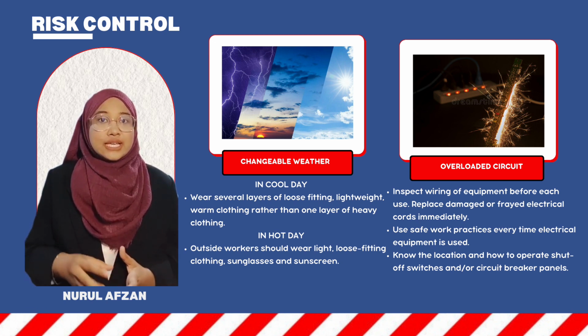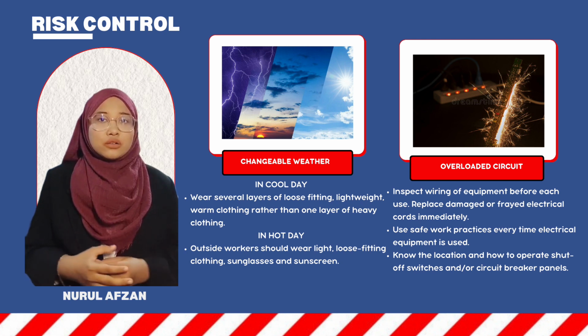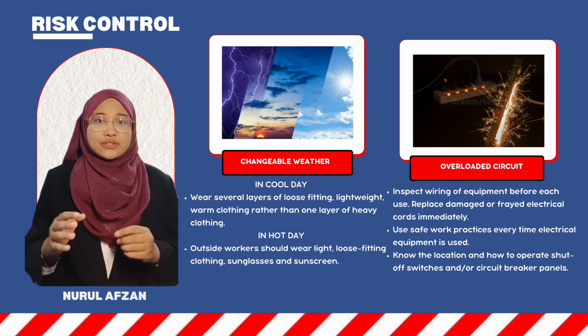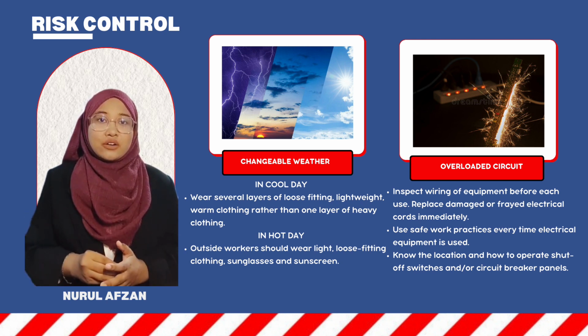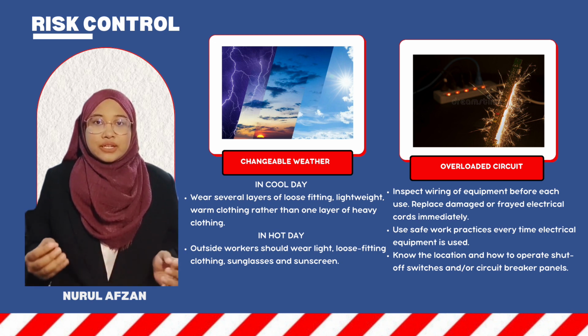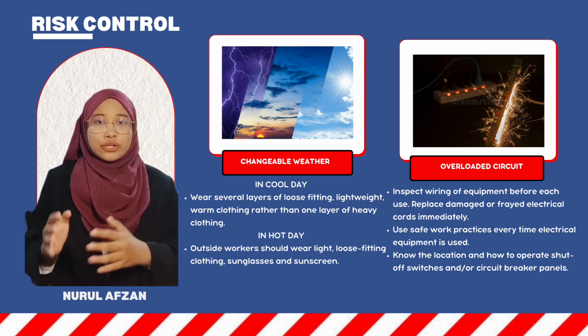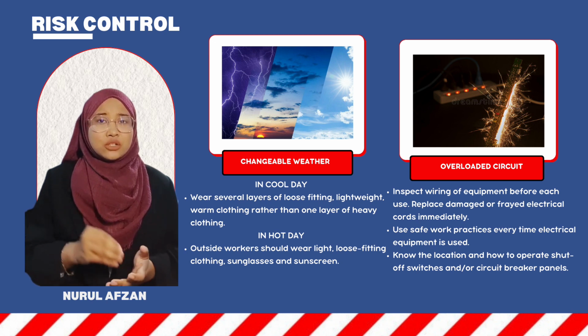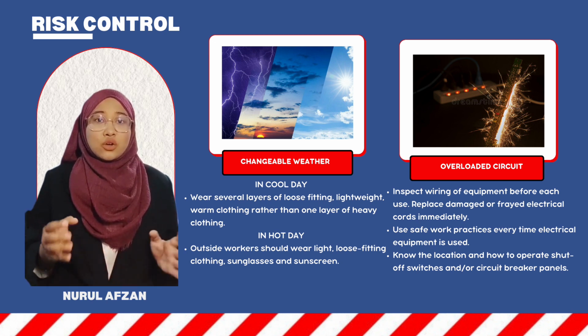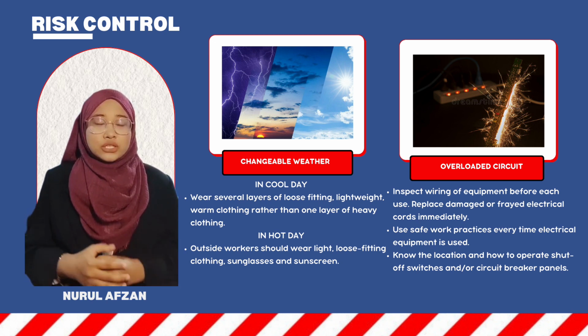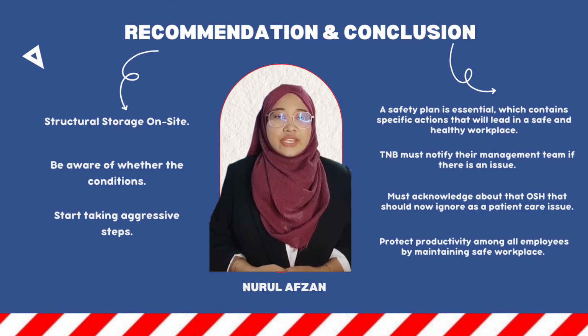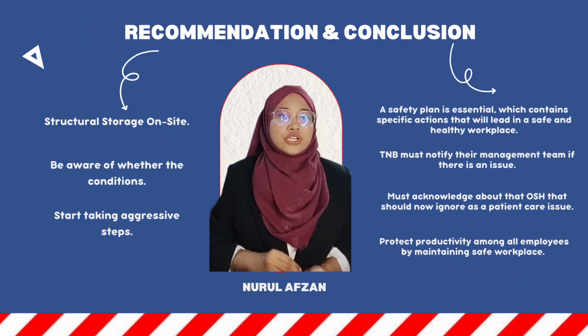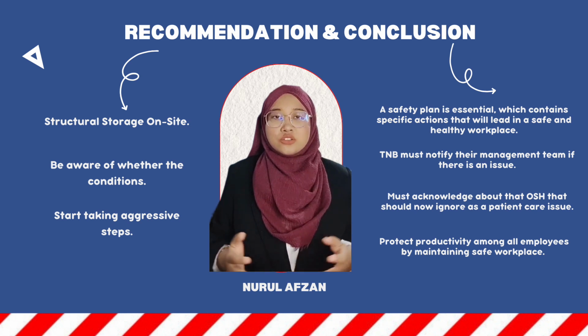In laboratories, it is essential to inspect all cords prior to each use, as corrosive chemicals or solvents might erode the insulation. Damaged cords must be repaired or removed from service immediately, particularly in damp locations such as cold rooms or near water supply. For recommendation, TNB should have structural storage on site, and the construction company should be aware of the expense of transferring any equipment, including highly flammable substances and paint.